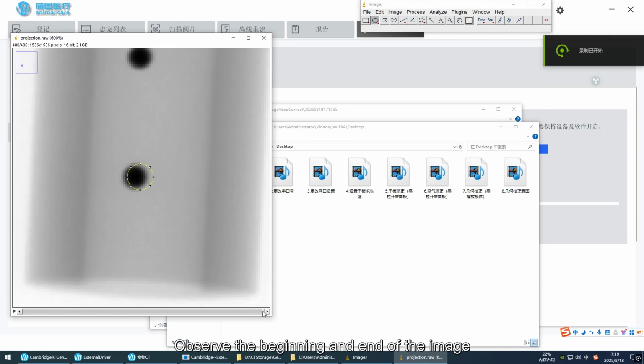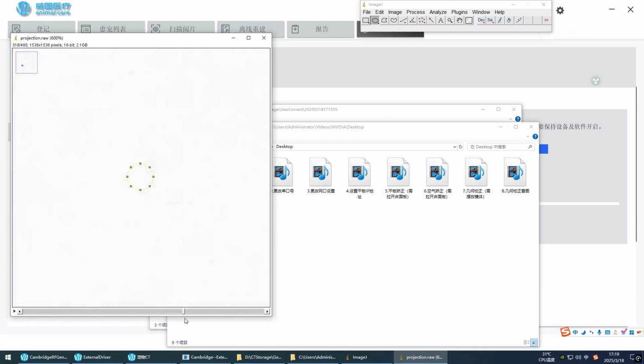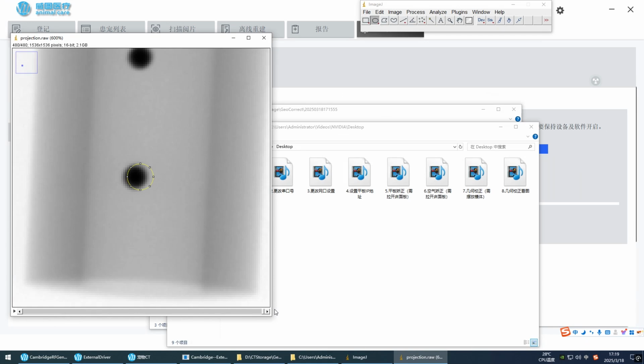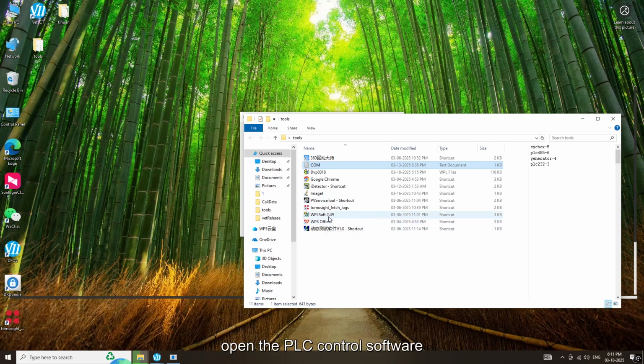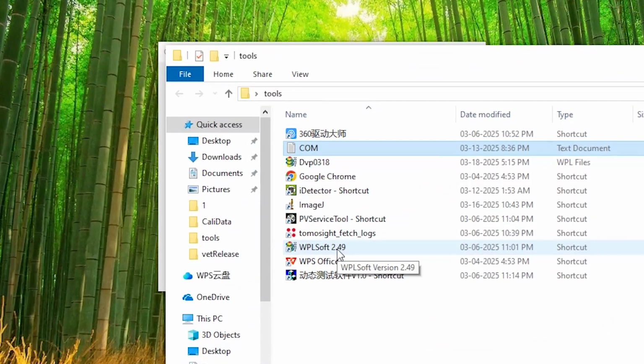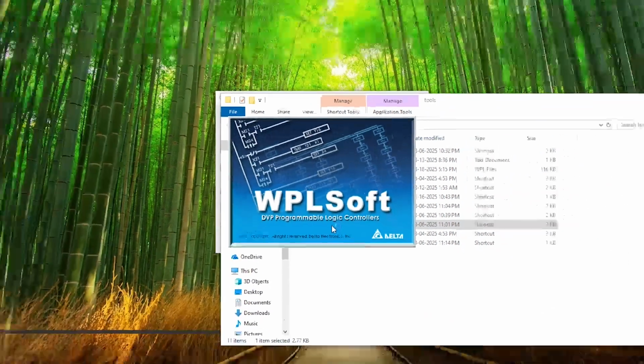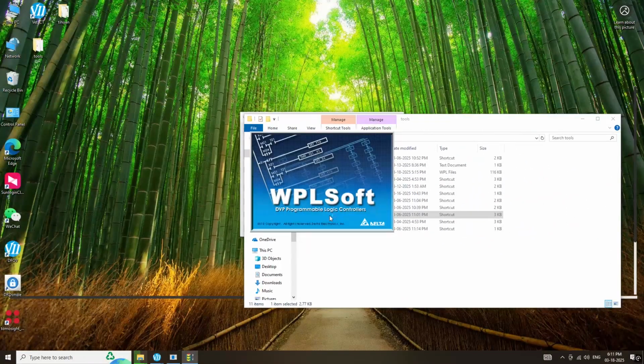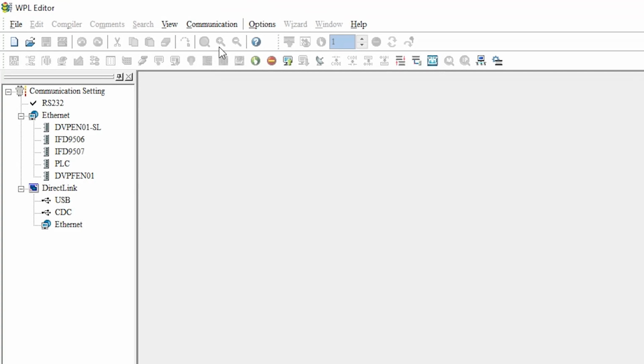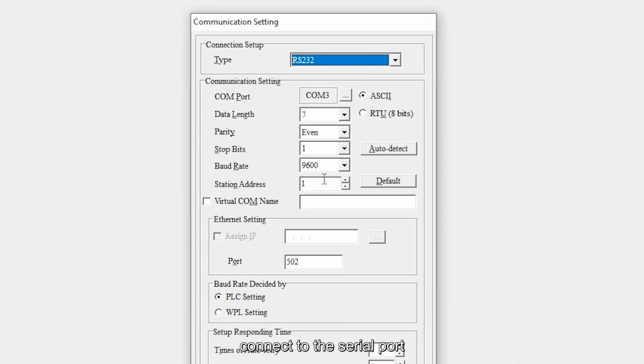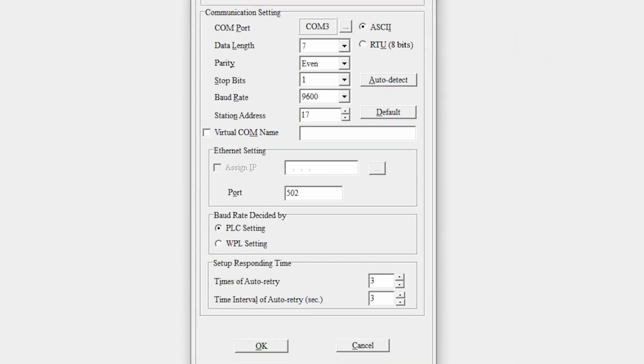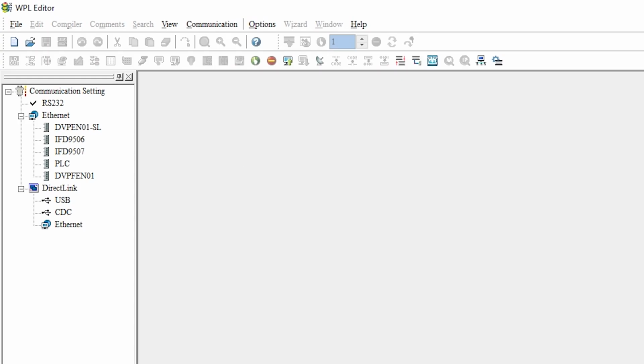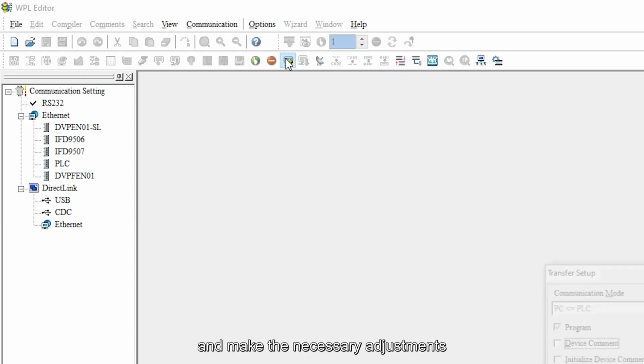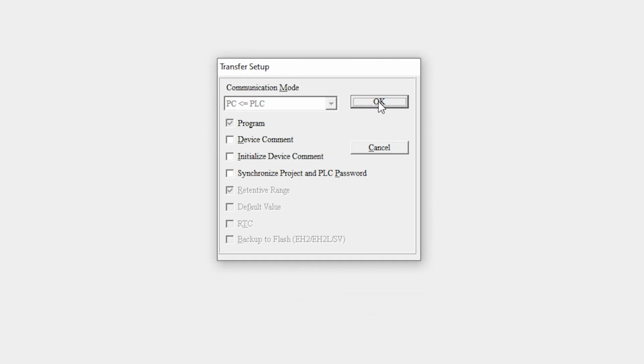Nine. Adjust Image 1. Observe the beginning and end of the image. If they align, the geometric calibration is complete. If they do not align, open the PLC control software, connect to the serial port and make the necessary adjustments.